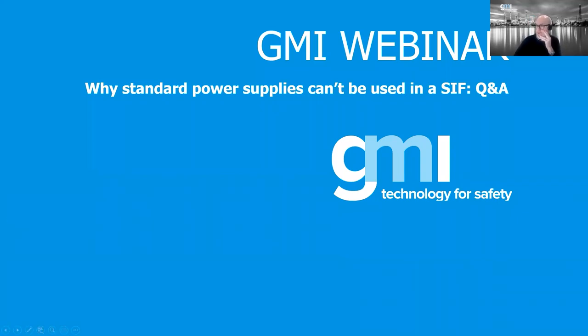We have a question from our attendees related to the slide for normally energized and normally de-energized load. Andrea. Okay, I didn't see this one. What is it? This slide means that different SIL levels can be achieved for different types of loads. We need a different configuration for our power supply system to get a SIL level for different types of load, normally energized or normally de-energized. SIL3 power supplies use only one power supply, it is SIL3 for normally energized, but it cannot be used for the same SIL3 in a normally de-energized configuration. Yes. It must be redundant in order to achieve SIL2 and probably triple if you want to achieve SIL3.